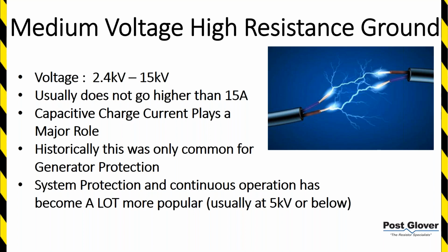Typically at medium voltage, you're going to have an issue with a lot of energy, potentially more energy than a low voltage resistor system. So you're going to have to worry about how much amperage you have matched to your voltage. Capacitive charging current plays a major role. We'll go into that a little more later, but basically the current you have for your resistor is going to be dependent in part upon the capacitive charging current.